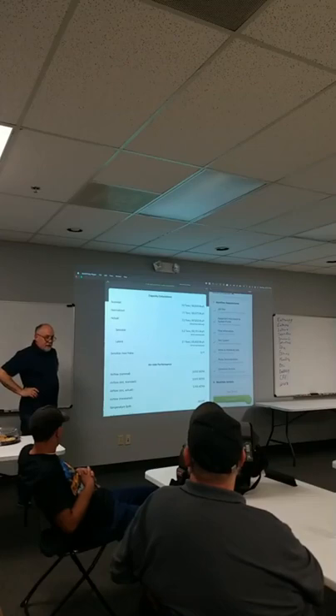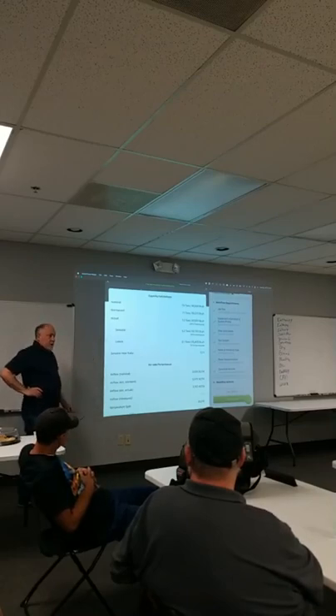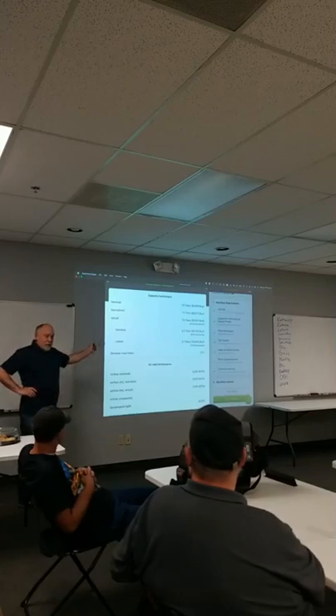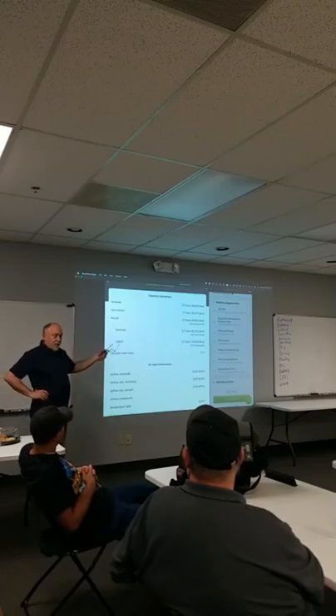Why is that? Depends on the latent, no? Depends on the latent load. Latent capacity is available when there's latent load to remove. Otherwise, the capacity goes unused. It's just sitting there, waiting for humidity to condense on the coil. If there's no latent load to condense, if you're above the dew point temperature, the coil's above the dew point, you're never going to do latent cooling. So most of the systems in Arizona are operating at 75 to 80% of their rated capacity because they're set at 450 CFM per ton and there's no moisture in the air to remove.